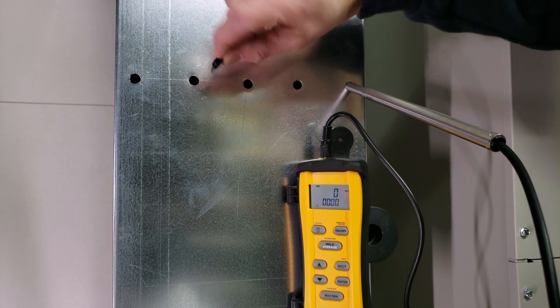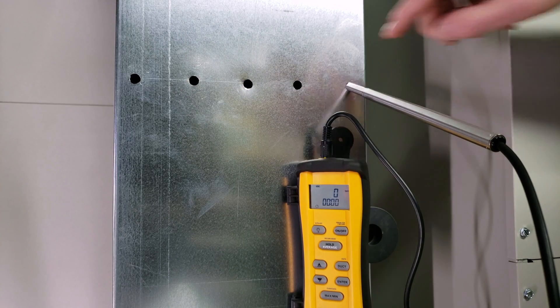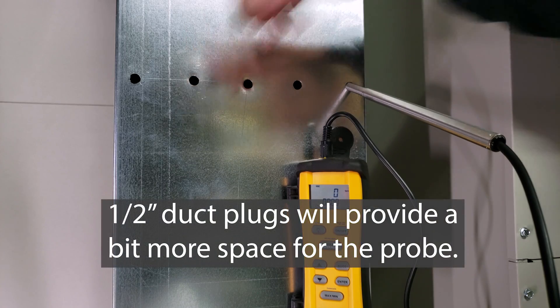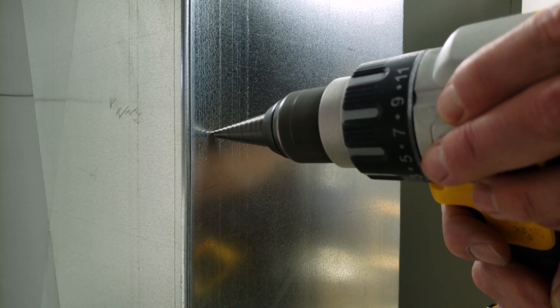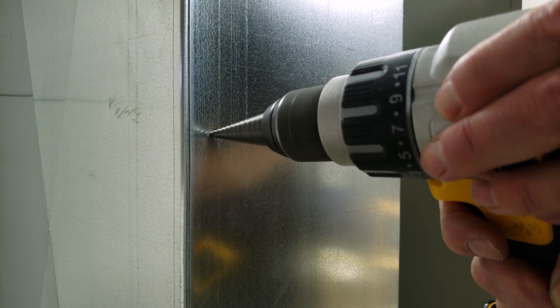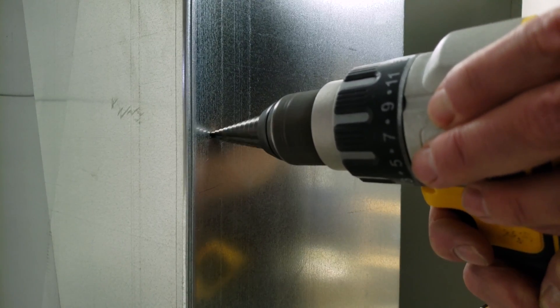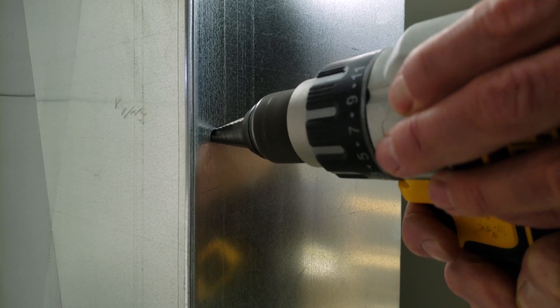Drill holes to the diameter of your duct plug, ensuring your probe fits. We're using three-eighths inch duct plugs. I usually use a unibit to drill into the duct. If you're not comfortable, put a washer on the unibit to stop from going too far. This is how I do it.